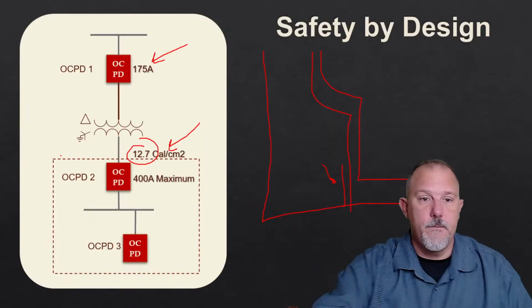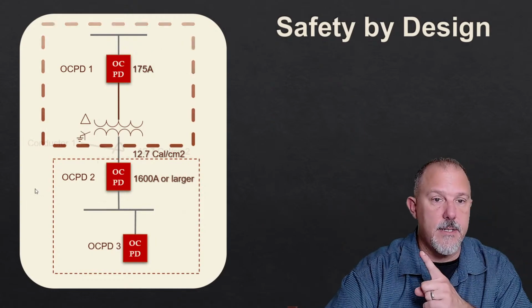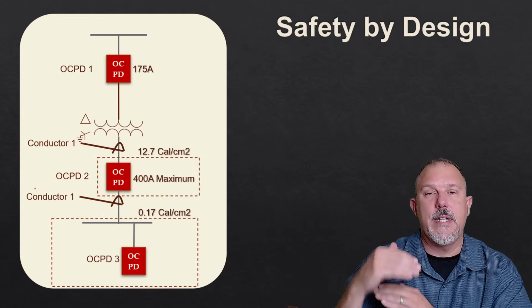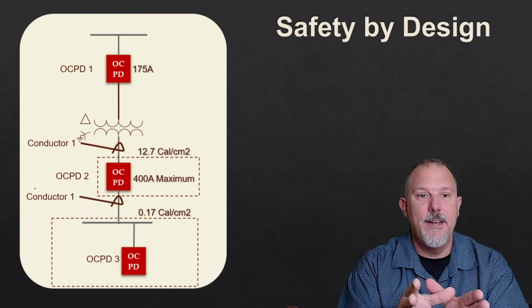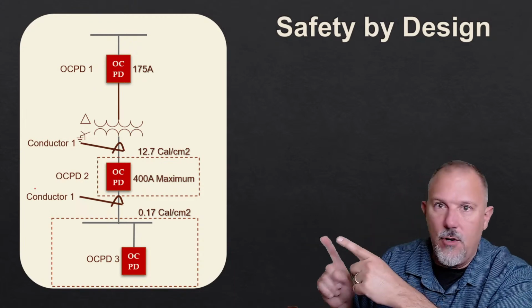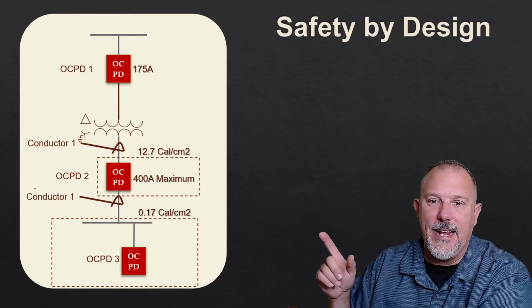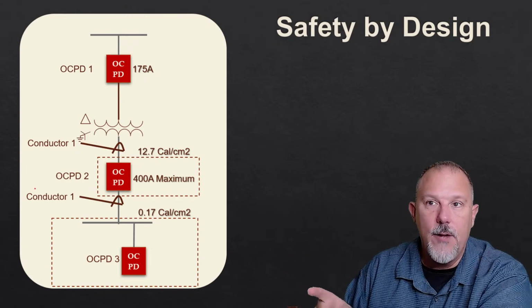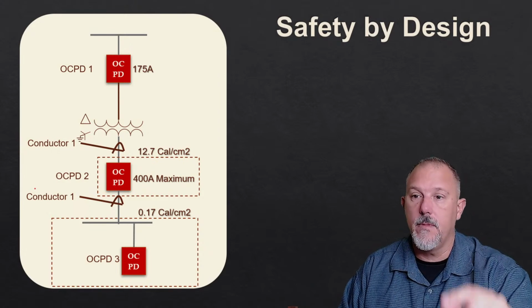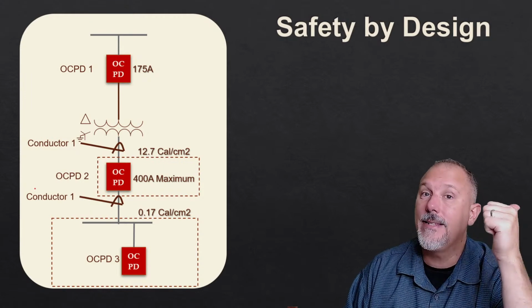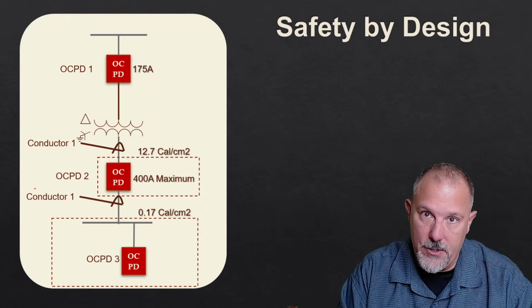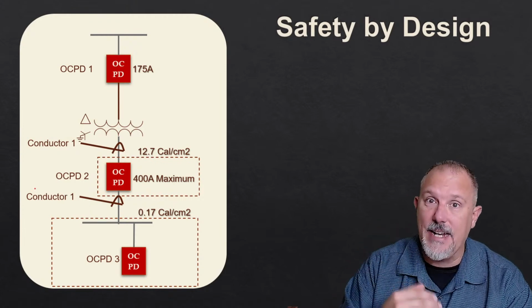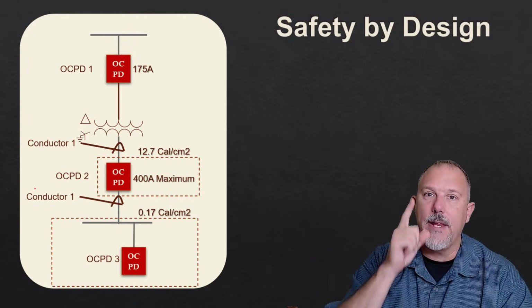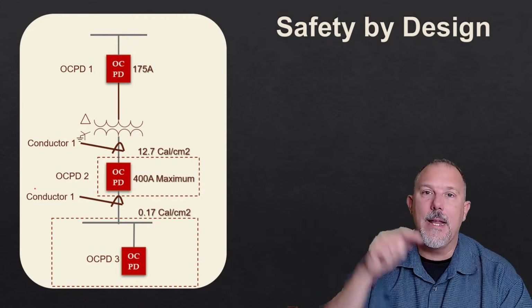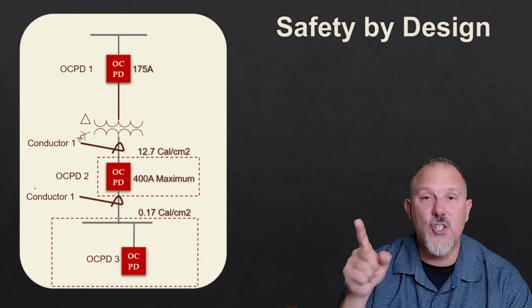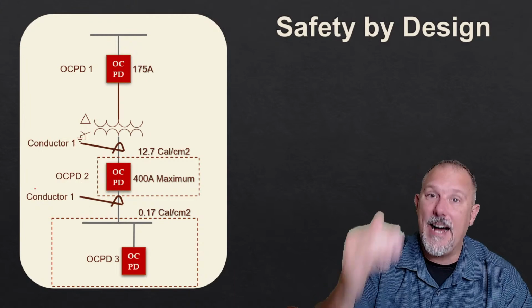So it's saying, look, if this is 1600 amps, then you're moving that main overcurrent device into its own enclosure. And why do we do that? Because now I can leverage that overcurrent protective device to calculate my incident energy in the first panel downstream of it. What have we done? Think about risk. Risk is likelihood and severity. What is the likelihood that I am going to have to do justified energized work in an enclosure that only has one overcurrent device, and that is the main? The likelihood is low. The incident energy is 12.7, so the severity is high.